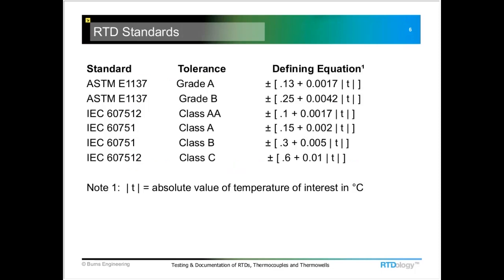And if we look at these interchangeability levels with some equations here, as an example, if we were looking at an ASTM standard and we wanted to calculate the interchangeability or this manufacturer tolerance at a given temperature, we just plug that temperature into this equation. If it's a below 0 temperature, you drop the negative sign and run through this, and it'll give you this plus or minus tolerance at that temperature.